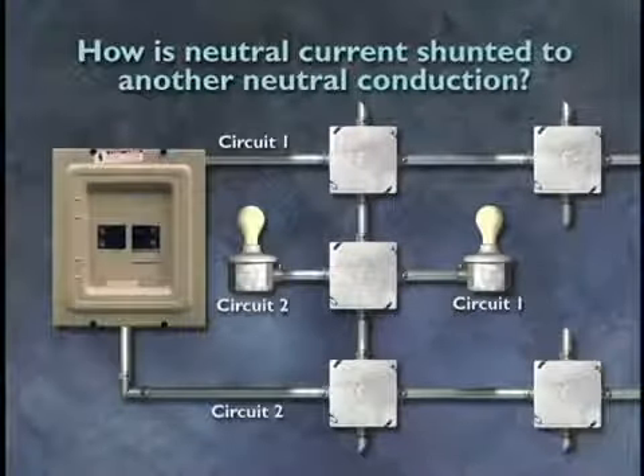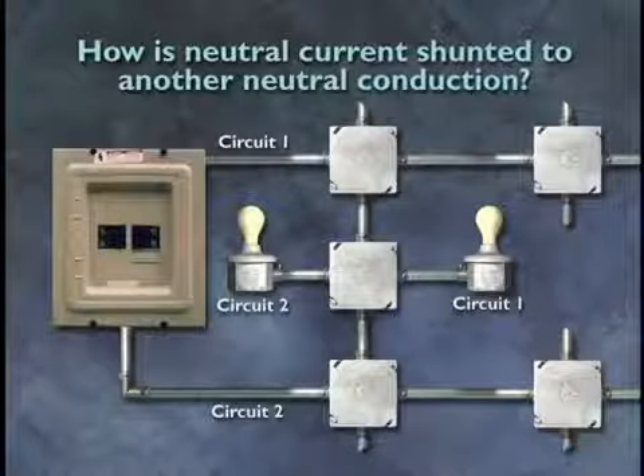The question is, how are neutrals in that shared junction box connected? The fact is, the misconnection of neutrals is the most common cause of elevated magnetic fields in school buildings today. Understanding why this happens and what to do to correct the problem is the single most important thing you can do to eliminate wiring errors and reduce EMFs.